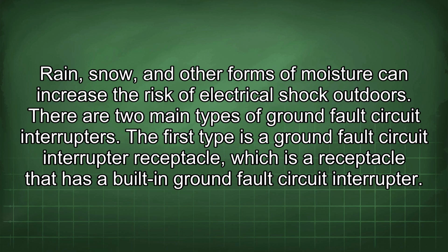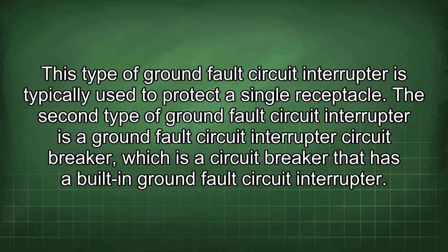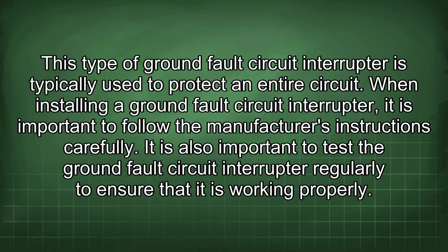There are two main types of ground fault circuit interrupters. The first type is a ground fault circuit interrupter receptacle, which is a receptacle that has a built-in ground fault circuit interrupter. This type is typically used to protect a single receptacle. The second type is a ground fault circuit interrupter circuit breaker, which is a circuit breaker that has a built-in ground fault circuit interrupter. This type is typically used to protect an entire circuit.